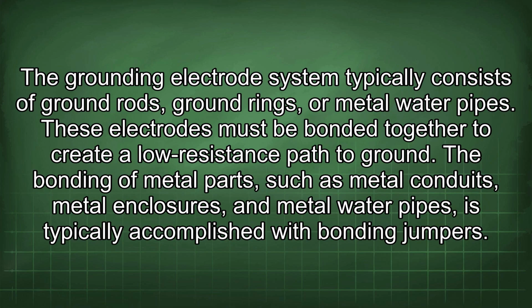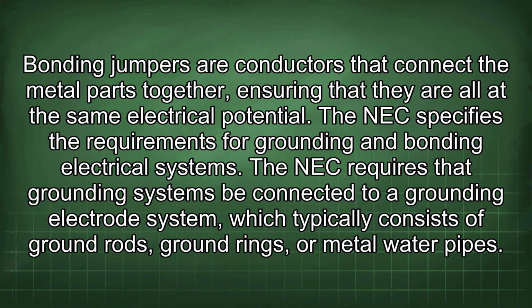The grounding electrode system typically consists of ground rods, ground rings, or metal water pipes. These electrodes must be bonded together to create a low-resistance path to ground. The bonding of metal parts, such as metal conduits, metal enclosures, and metal water pipes, is typically accomplished with bonding jumpers. Bonding jumpers are conductors that connect the metal parts together, ensuring that they are all at the same electrical potential.